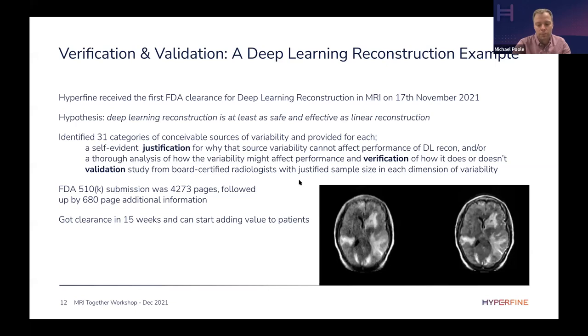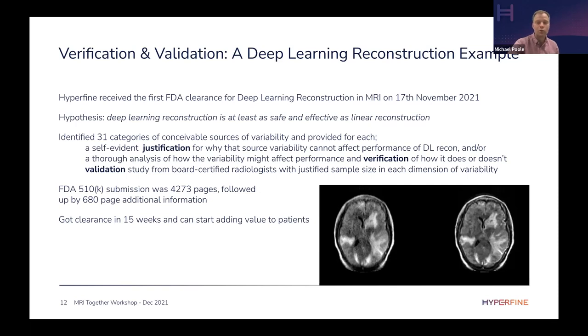All of these studies combined give you great confidence when you prove the hypothesis. We really believe that process mirrors good science, and looking at sufficient sample sizes is extremely important. We ended up with a submission that was over 4,000 pages long just for this one change to the product — everything else in the MRI device stayed the same. The FDA came back, asked questions, looked at all our scientific results and our theory of deep learning, we provided more verification and justifications — another 700 pages. But in 15 weeks from submission to clearance we got that clearance and could put significantly better images into the product and start adding value to patients.